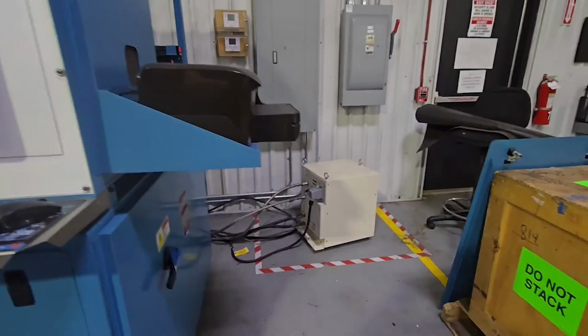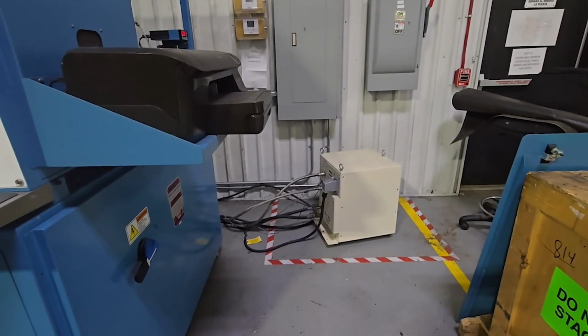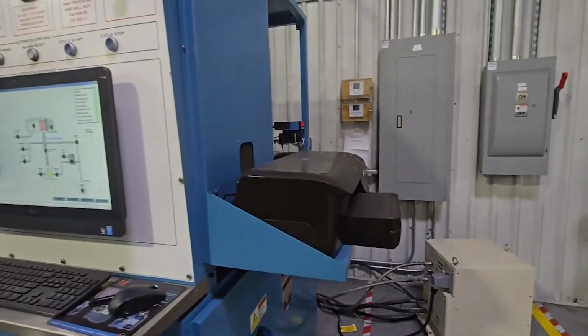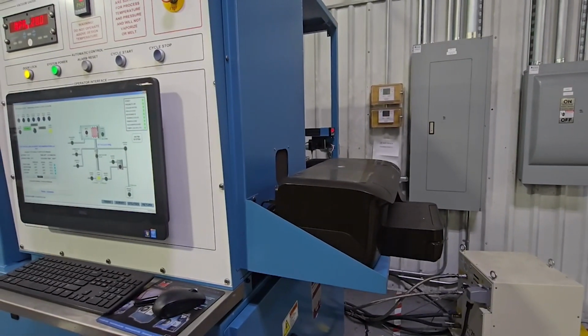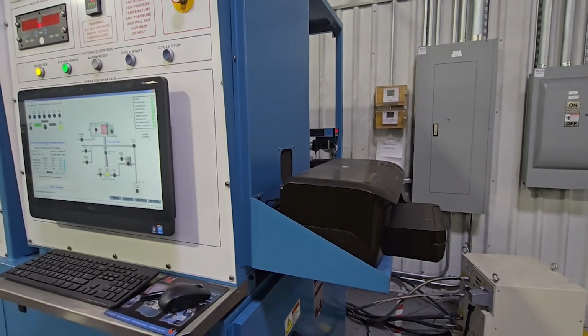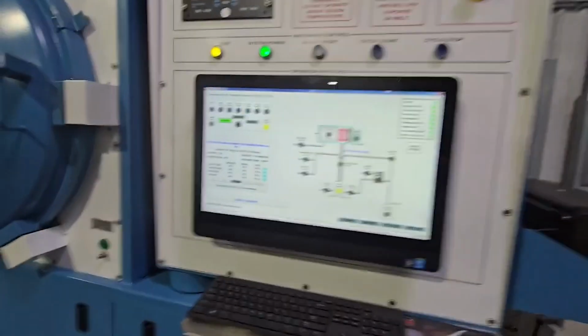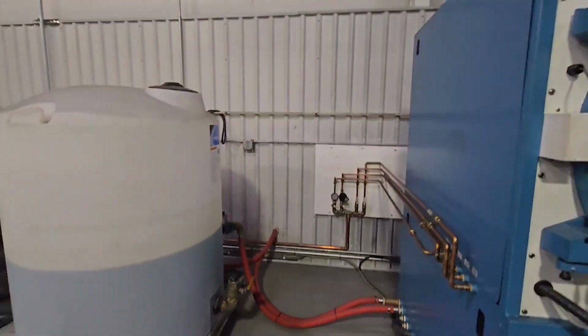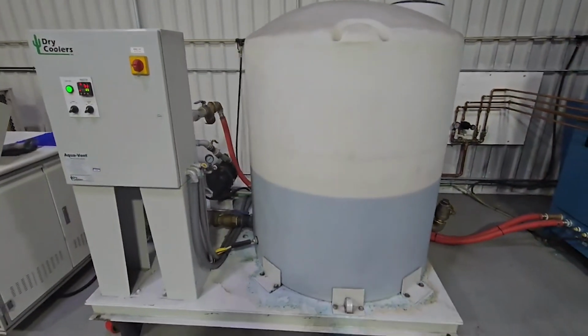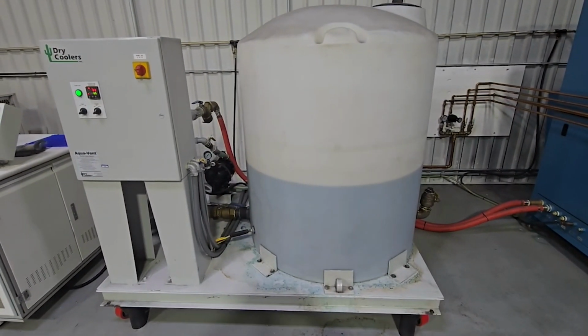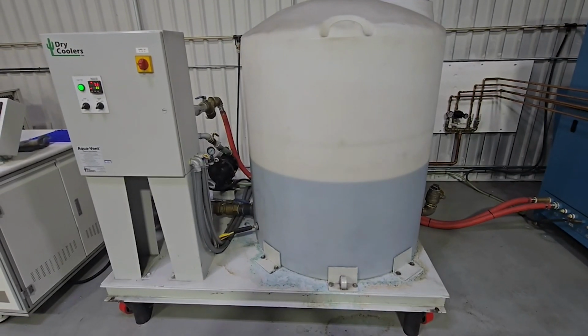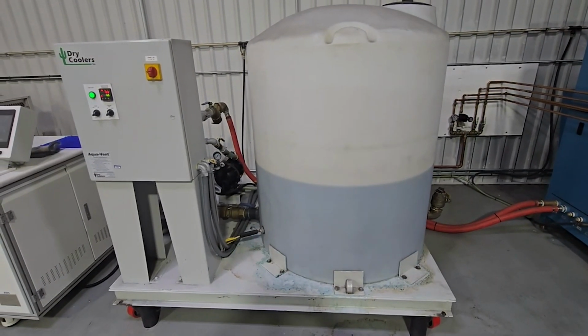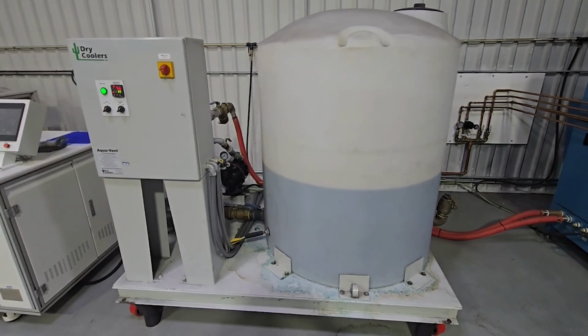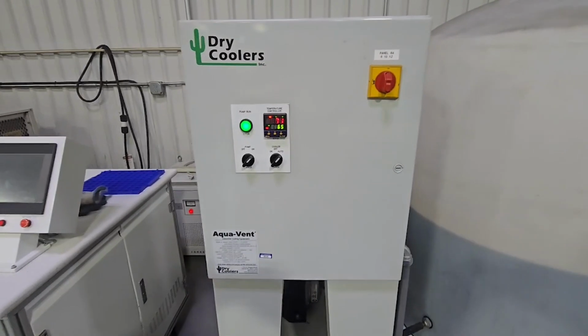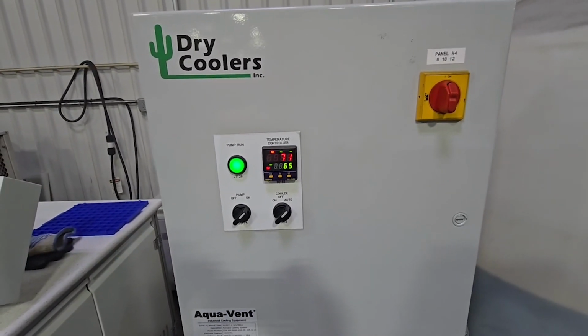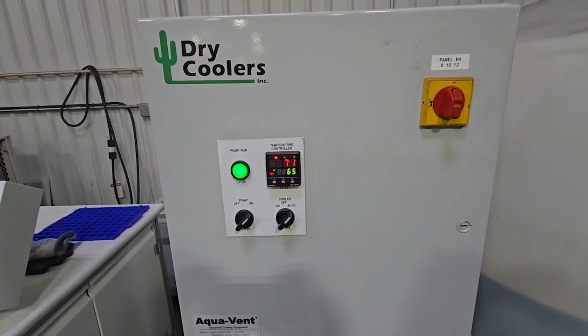You can see the cryo pump sits next to the machine, very compact. It does have a printer, that way you can print out vacuum cycles for your quality control. Sitting to the side is your coolant tanks, which is a mixture of purified or filtered water with glycol. It's a closed loop system, so it has very little evaporation. Right next to that, you have the control for the external heat exchanger, where you can set the temperature, and it controls the on and off of the heat exchanger as well.